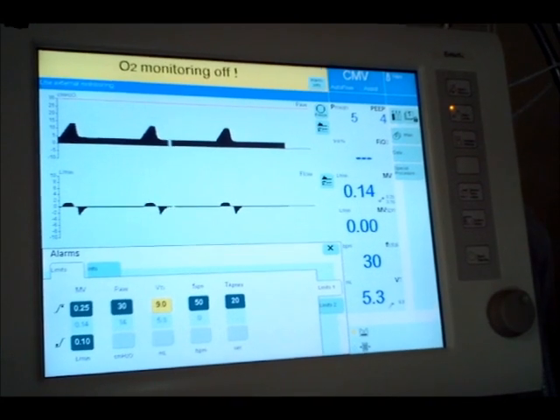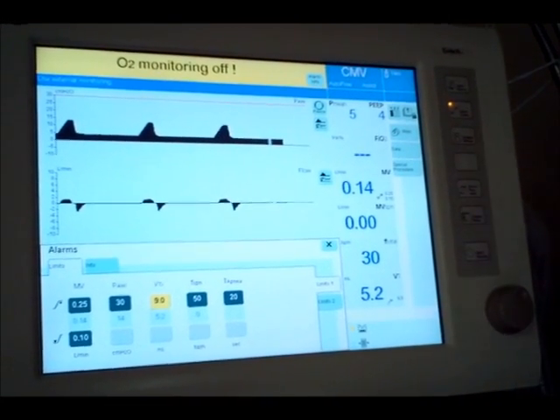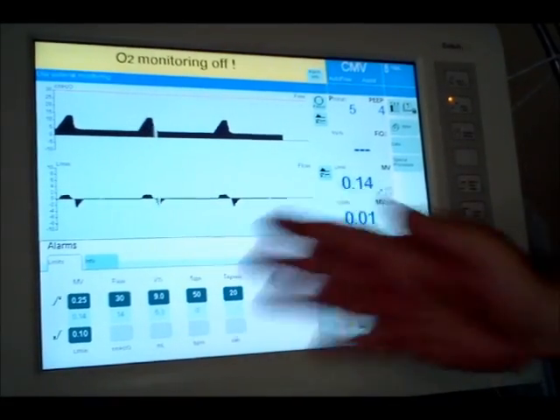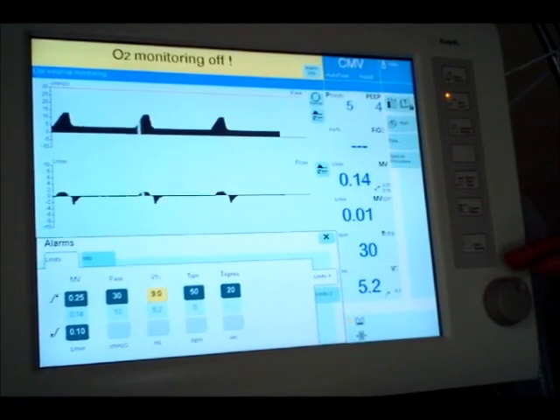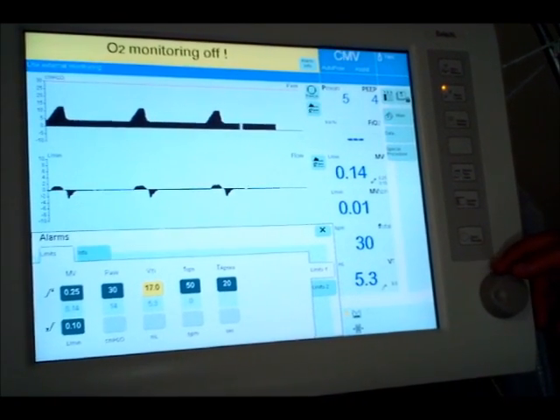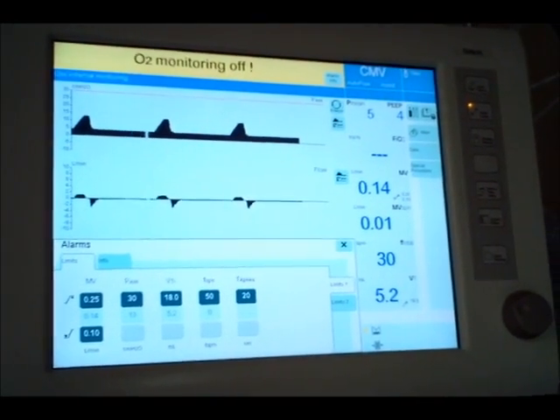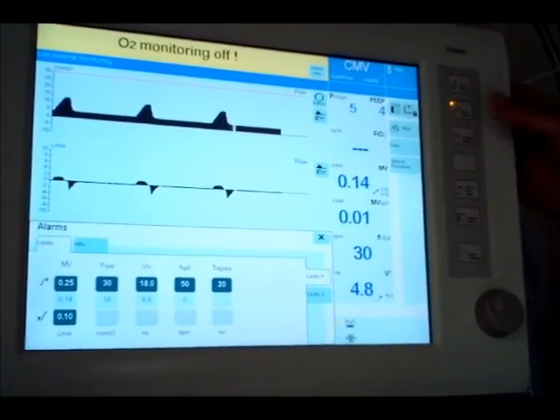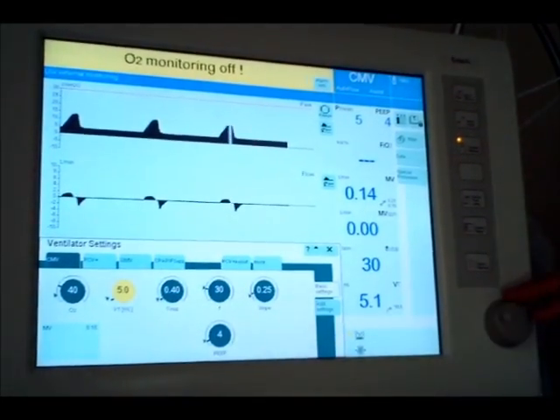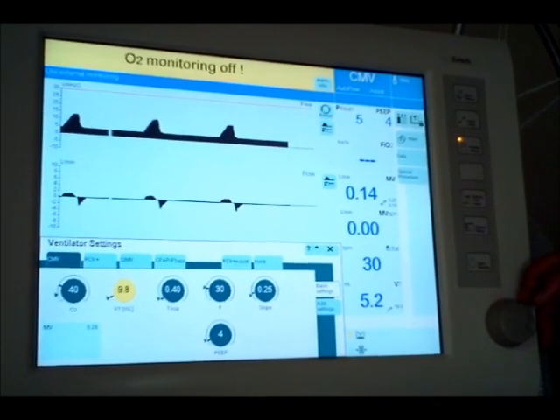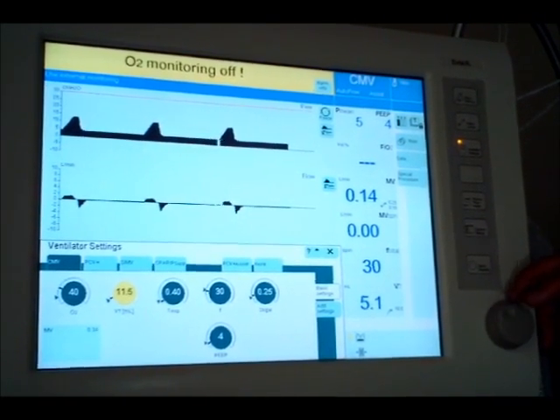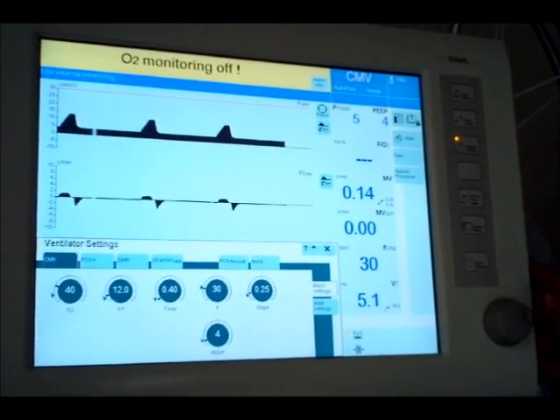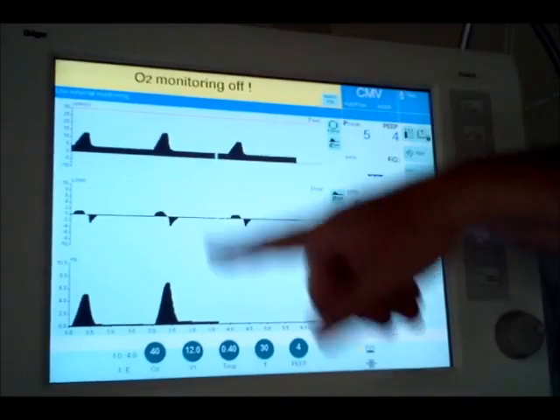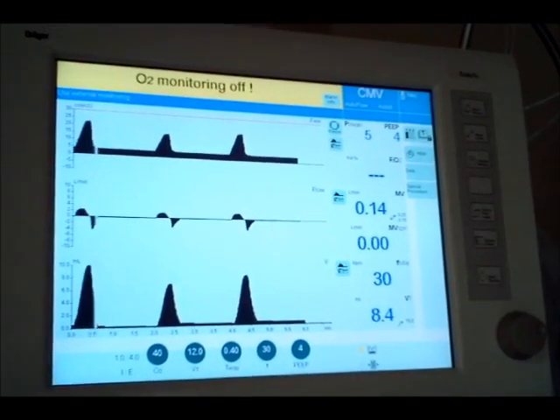So I'm just going to go ahead. I know I'm going to set tidal volume 12, so let's do 1.5 times that, so about 18. And again, if you start talking or you do something else after you've selected it, you need to select it again. Yellow's an important color on this ventilator. All right, so now I have my high tidal volume alarm set. I'm not sure what my other alarms are going to need to be set at, so I'm going to go ahead and get my new setting. What was it, 12? Okay. Now we should see a higher pressure there. We should see a higher volume. Probably our flow curve is going to change a little bit.